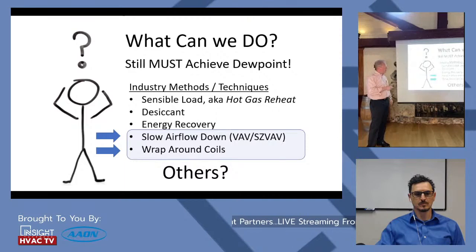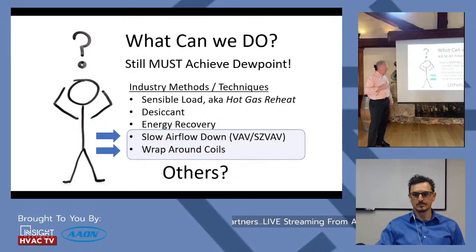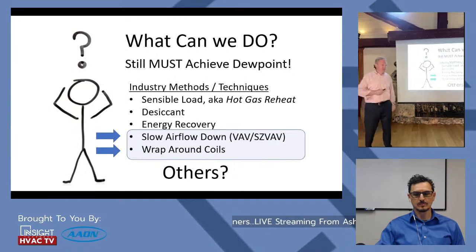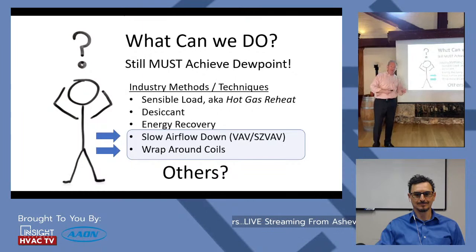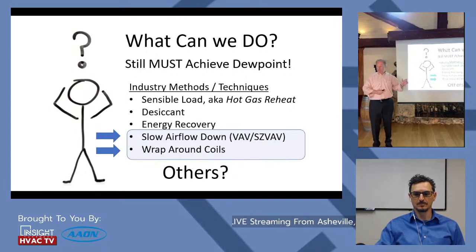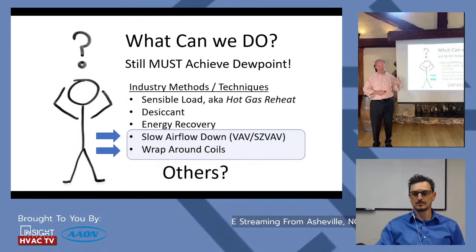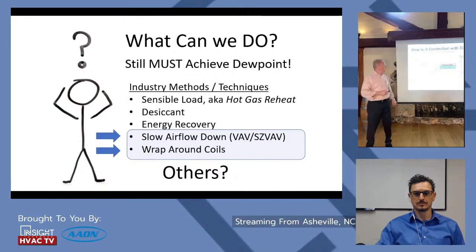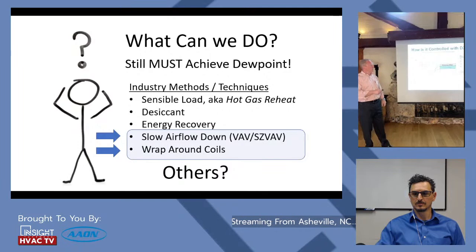Summary: we must always achieve the required dew point. Latent design machines can control down to about 42°F dew point; I have some controlling to 38°F, but that leaves only a 6°F approach before freezing — very tough to control. Sensible-design machines typically control to about 60°F dew point. With only 25% outside air on a semi-humid day, I showed how a system can fail. Below 42°F dew point, start considering desiccants. And 55°F dew point is easy under light outside air load — but add significant outside air and any machine will struggle.